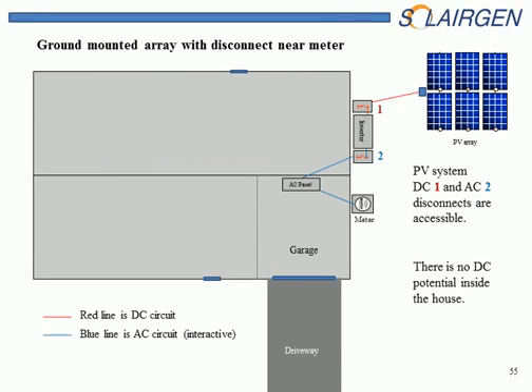And this is the PV system that you really want to see if you're approaching the structure in an emergency. The PV array is on the ground, the disconnect is on the outside of the structure, and so is the AC disconnect. So very easily we can isolate all of this DC energy from the structure.